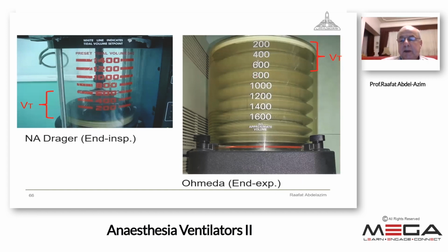Here we can see two types of ascending bellows ventilators. These are Ohmeda, and the other one is Draeger with ascending bellows. But the movement of the bellows starts on the one on the right side from the top. The grading or the scale starts from the top by 0, 200, 400, and so on. So it will go during inspiration from this point down to reach the set tidal volume. During expiration, it will go up. It is an ascending bellows ventilator.